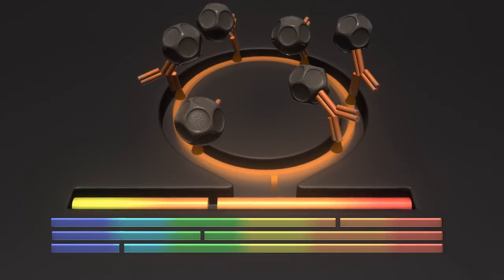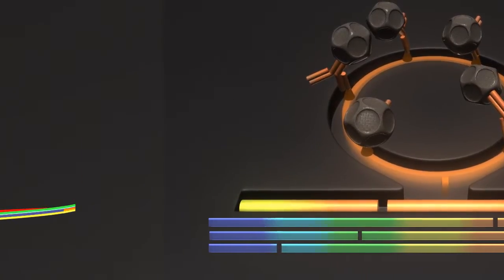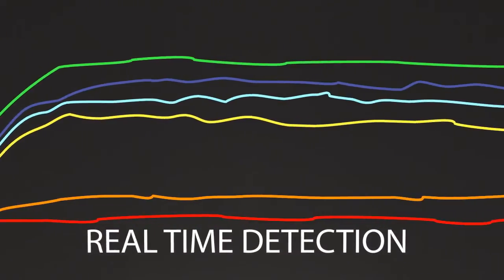The resonant shift is proportionate to the mass of material bound to the sensor and is monitored in real time throughout the assay workflow.